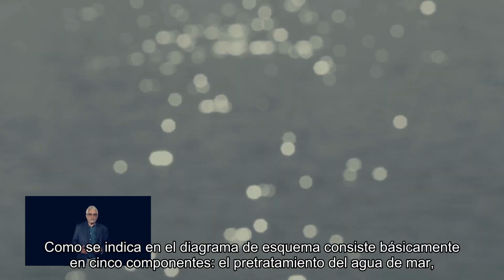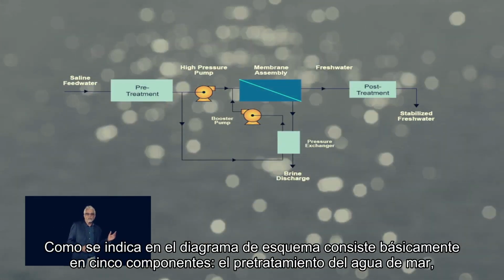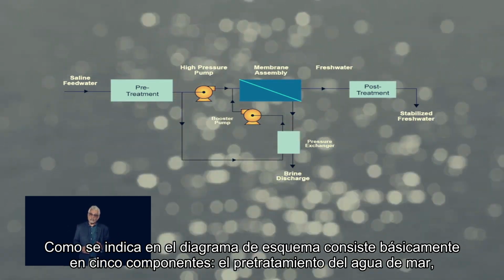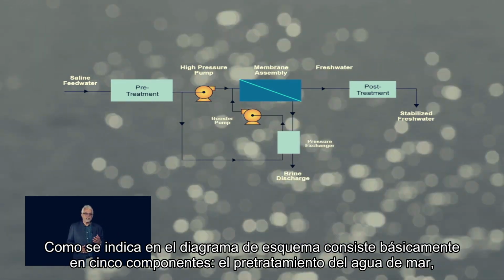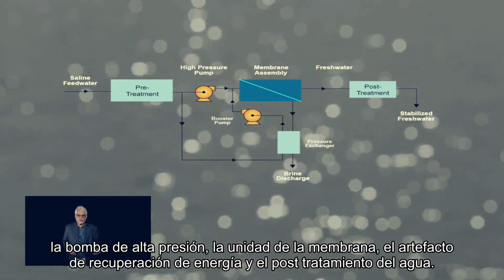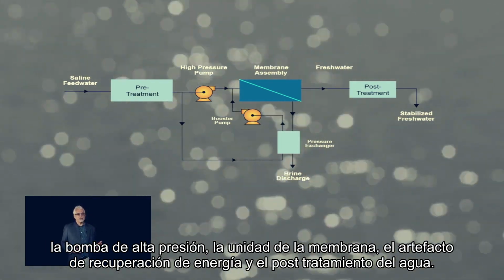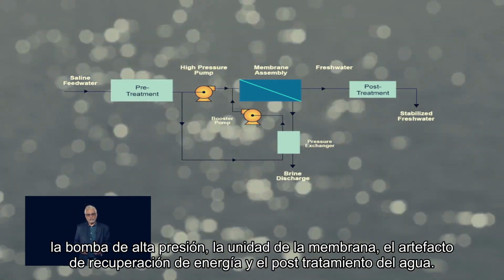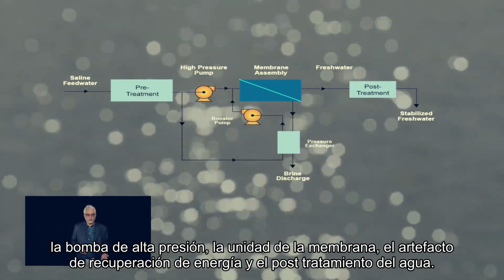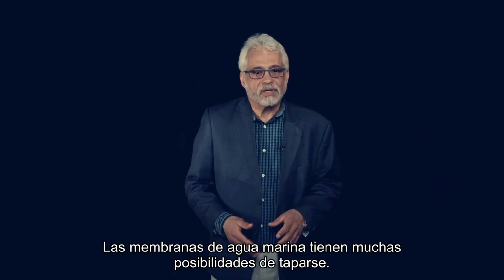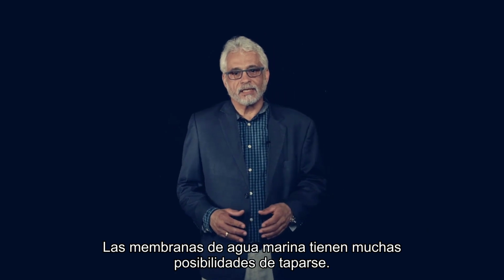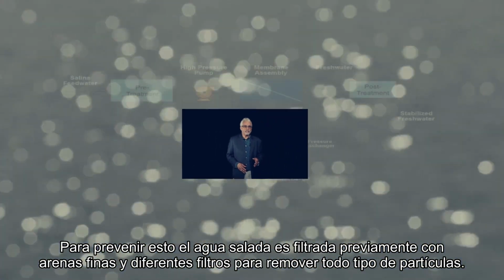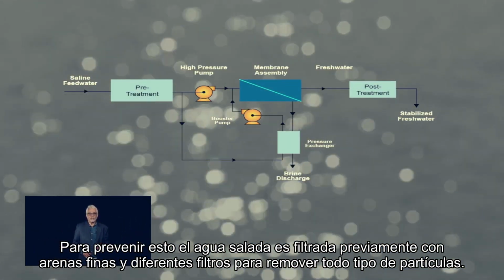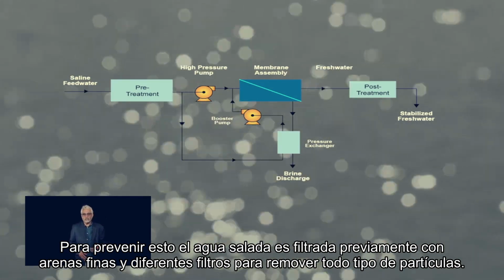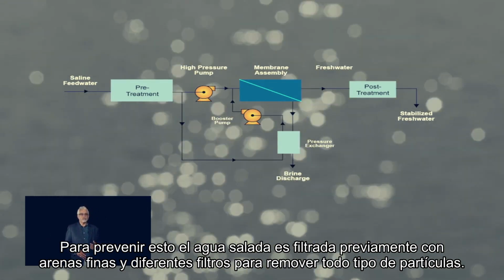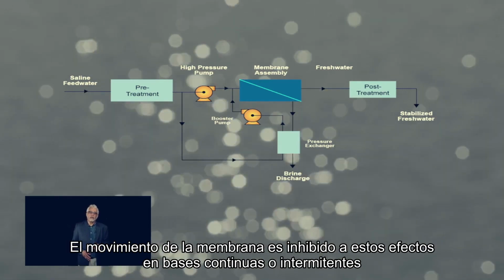As indicated in this schematic flow diagram, the seawater RO plant consists basically of five components: the seawater pretreatment, the high pressure pumps, the membrane separation unit, the energy recovery device, and the post-treatment of the product water. Seawater membranes are very prone to fouling and scaling, and to prevent this, the seawater feed is filtered in the pretreatment section with fine sand and multimedia filters and with cartridge filters to remove all kinds of particles.